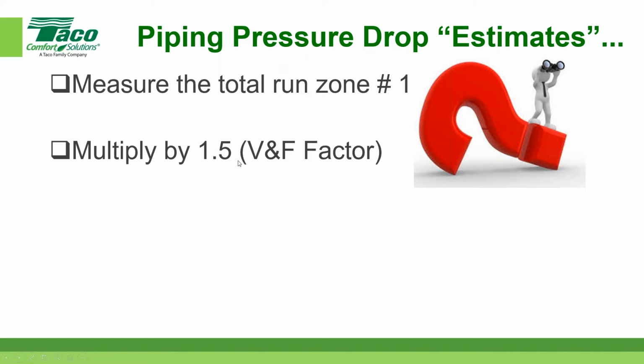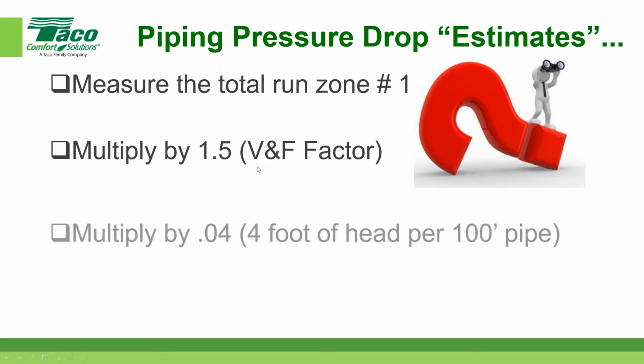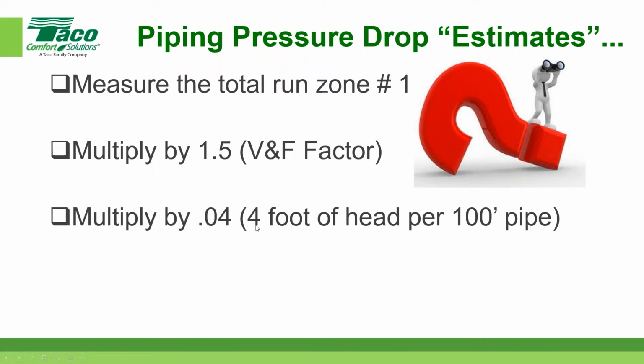So the first oversizing here is you take the total measured run of the first zone and you multiply it by 1.5. That means you're adding a 50% valve and fitting factor. And guess what? That 50% is a big fudge factor typically, and not in every case, but in most cases it tends to oversize. Another thing that oversizes is to use the 4 foot of head per 100 foot of pipe. It gives the assumption that you're maxing out the flow of that particular size pipe.